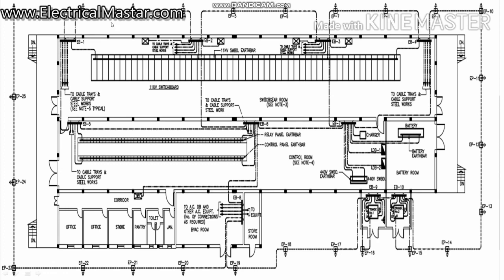Now we will see how the earthing is connected in this substation. See here, outside of the substation, everywhere they put EP1, EP2, EP3. Likewise, all the substation surroundings are connected with EP numbers, and finally it ends up with EP25. EP means earth pit. So a total of 25 earth pits are connected, and all the earth pits are interconnected one by one, starting from EP1 and ending at EP25, and finally it returns back to EP1.